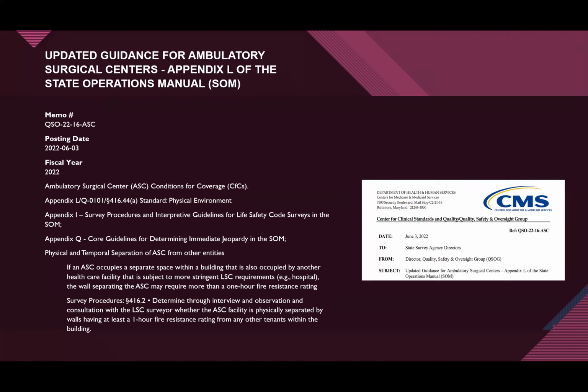And then it has survey procedures and it talks about interpretive guidelines. And so when you look at the interpretive guidelines, it will list the questions the surveyors are going to ask you. And this is why I've said this is an open book test, because we can predict what questions they will ask. Now, the survey universe is many, many, many questions. So depending on the knowledge of the surveyor, the experience of the surveyor, your past deficiencies, the size of your ambulatory care center, and the level of anesthesia that you give, they will pick different questions, but they will always talk about 1 hour separation. They will always talk about fire alarm. They will always talk about generator, and they will always talk about sprinklers. Next slide, please.